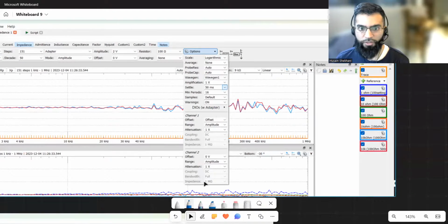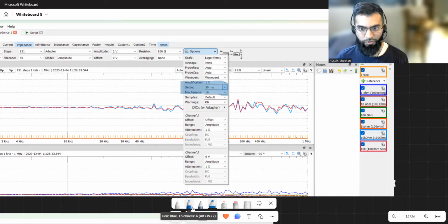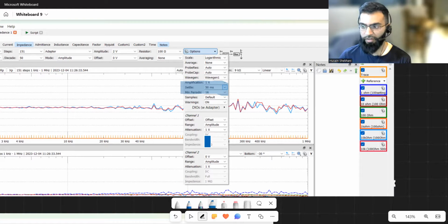Here I want to show you other options that you have for improving the measurement. You have averaging. There's both time averaging, like a minimum of 10 milliseconds of data, and also a number of samples taken. There's also the settling function, and I want to talk about this for one moment. The settle is very important for high Q resonators because they take a while to settle down once you drive at that frequency. So in order to get stable results, you want to experiment with what settle values would be best. Obviously, for a resistor, there's no settle value. It is what it is. But for a resonator, you will want to understand what the settle values are.